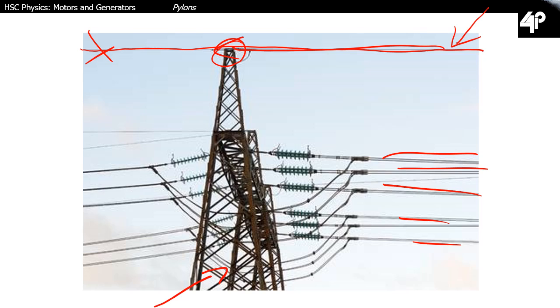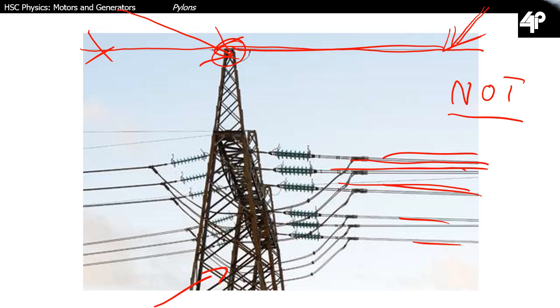So if we do get a lightning strike to the static line, so sometimes you hit the line, sometimes you hit the pylon at the top where the line joins it, but you've got one of two things that can happen. So the first thing to notice here is that the static line is not insulated from the pylon. Okay, it's not insulated from the pylon, and that's what's making it different from the transmission lines here, which are heavily insulated from the pylon.